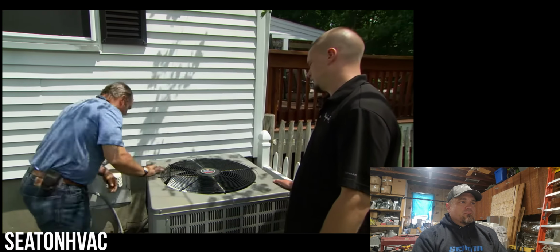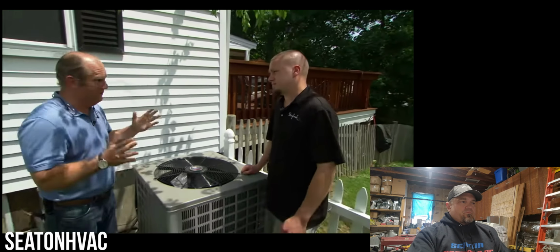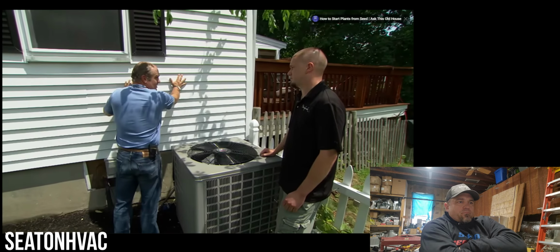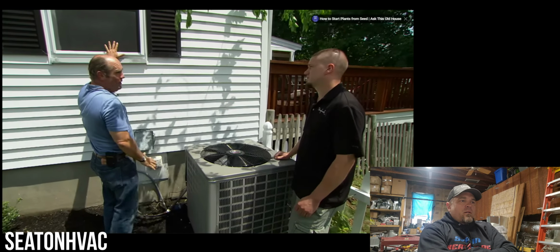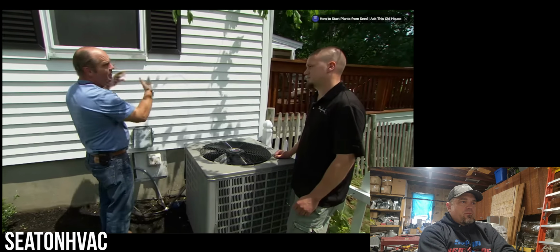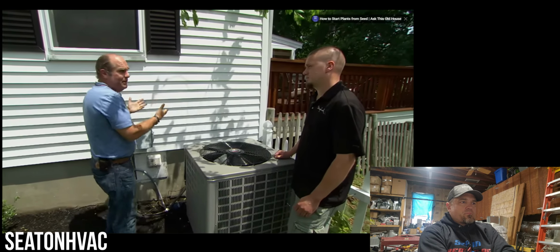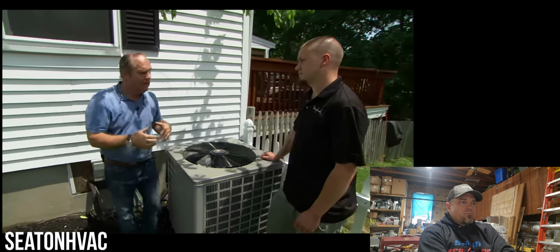All right, so let's see what you got here. You have a 4-ton system. 4 tons, is that a lot? Well, the amount of cooling power you need is a function of the load of the building, and there are some variables. How much insulation is inside the walls? What type of windows? Are there storm windows? How big is the building? And where's the building? How hot does it get on the hottest day of the year? I'll tell you, a rule of thumb for me around here with a building like this, I would expect to see a ton of cooling needed for every 500 to 600 square feet.